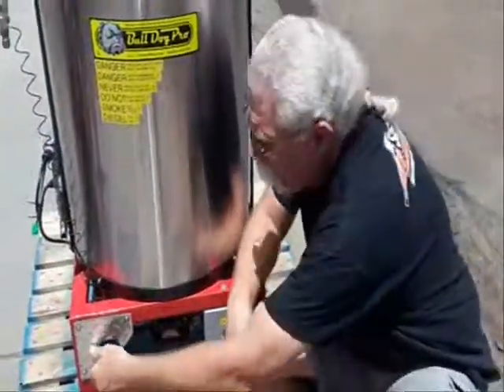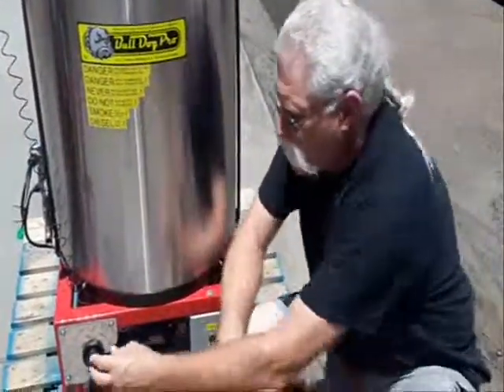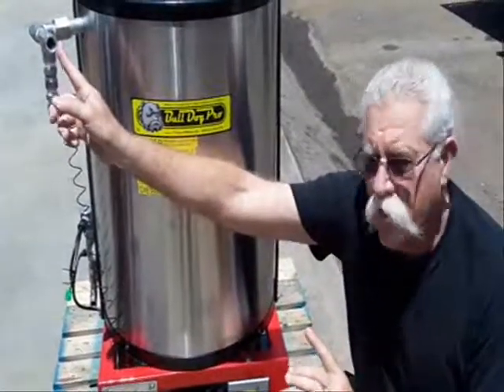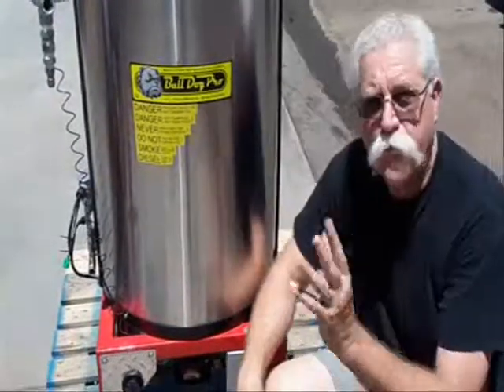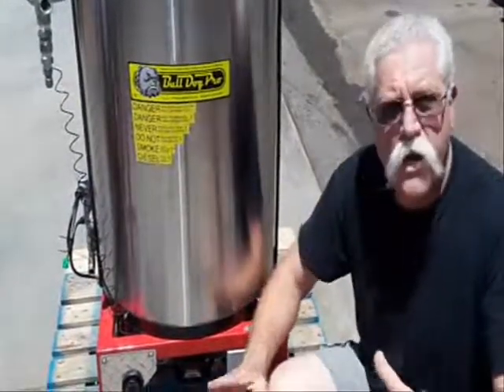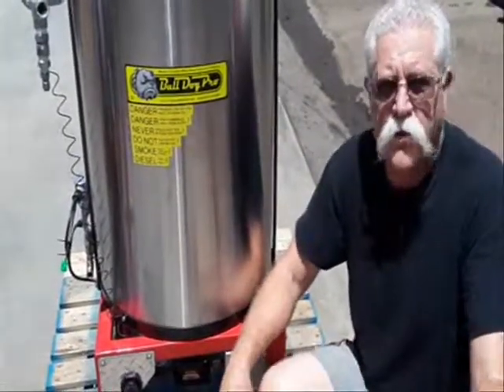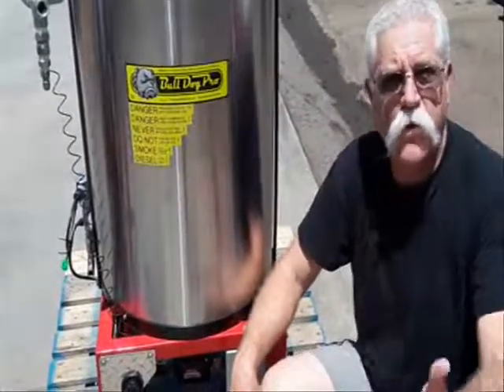If you turn down the temperature control, the heater should shut off even with the gun open. You turn it up and you should be good. Remember, this is a high limit switch. You're going to set this for the maximum temperature that you're trying to use. Your temperature gauge is going to be right here. Never set the temperature for more than you're expecting. If you want 120 degrees and that's all you want, then only turn it to 120. If you want 200, turn it to 200.